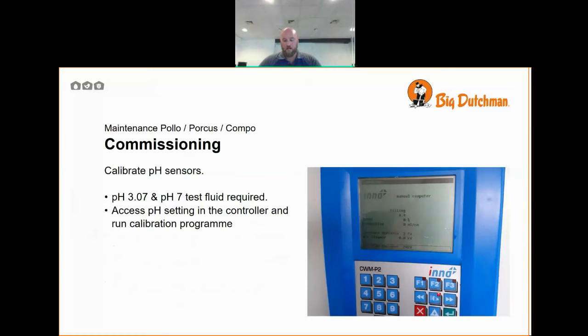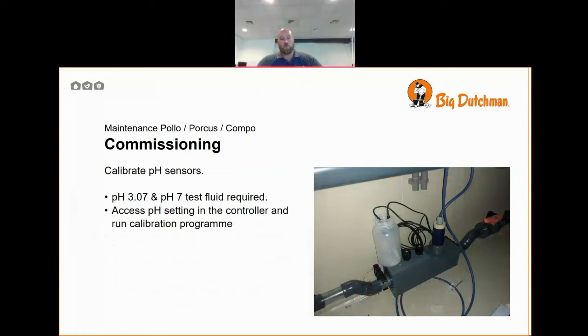We'll also calibrate the pH sensors. To do this, we use a pH of 3.07 and a pH of 7 test fluid. We then run the calibration program that is built into the controller under the air scrubber settings.